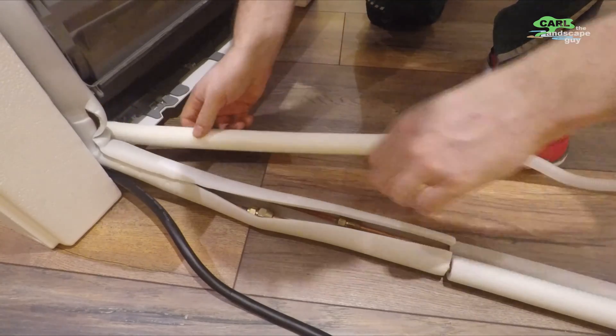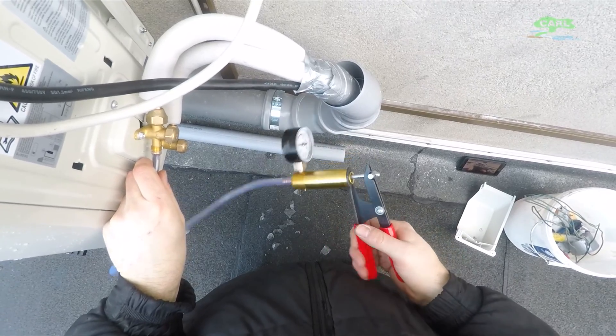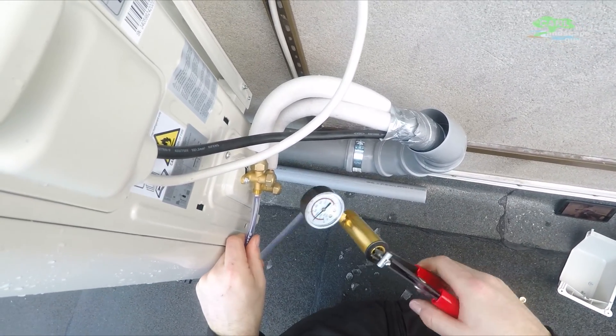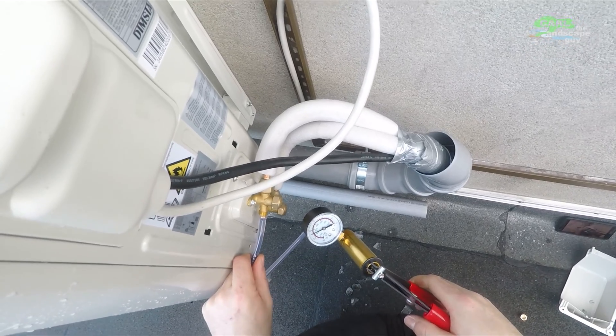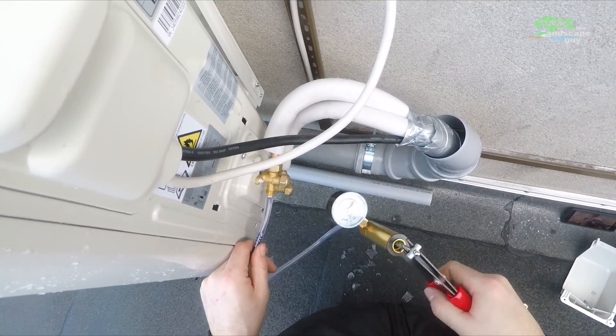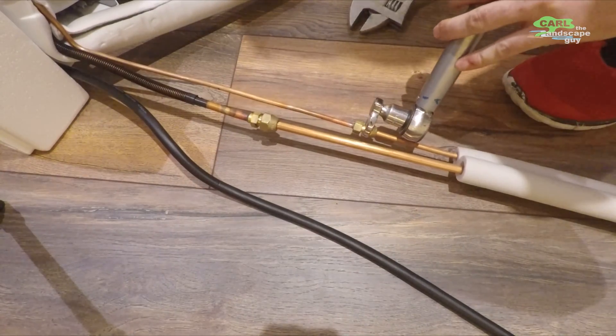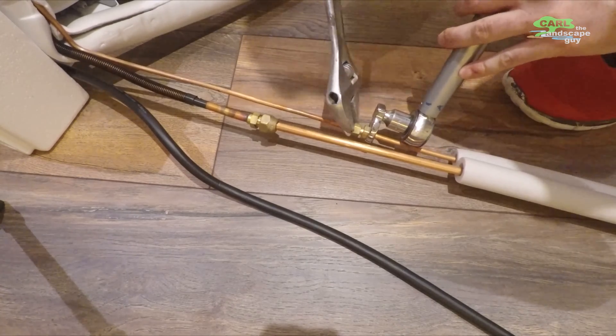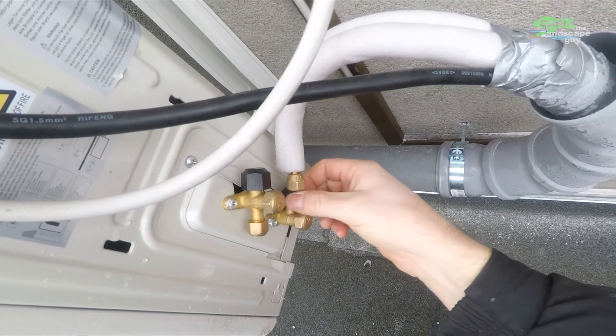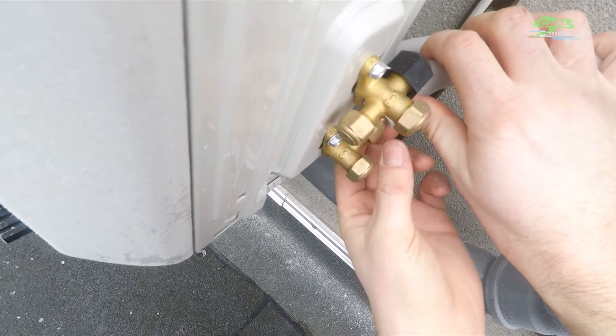Naturally there were critical comments about using a hand pump to create the vacuum in the lines. I can understand that, but I just wanted to know if it works — and the system runs really well and quietly since I followed the torque specifications of the screw connections exactly. I'm positive the connections are tight. Next time I install an air conditioner I will get an electric vacuum pump or hire a specialist.